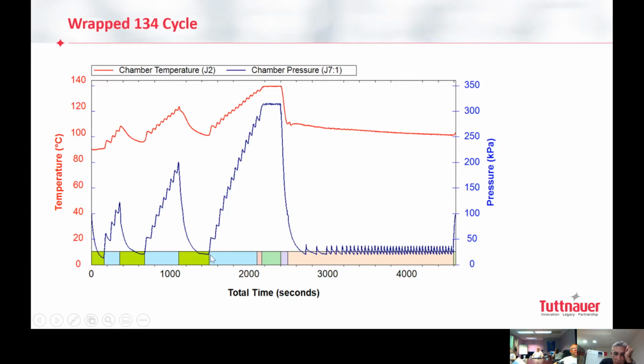Up to this point, you see my pointer, my mouse? Yes. Up to this point, we call this stage the air removal stage. Once we completed the air removal, we finish with that. We start with the second stage, which is the heating stage. We start heating up to the sterilization temperature, which is in that case, 275 or whatever it is, or 250 Fahrenheit. Of course, how it is done, we have the steam generator / vaporizer. We are pulsing small bubbles of water into a very hot place, and then it gets vaporized, expands, and just becomes steam and comes into the chamber.